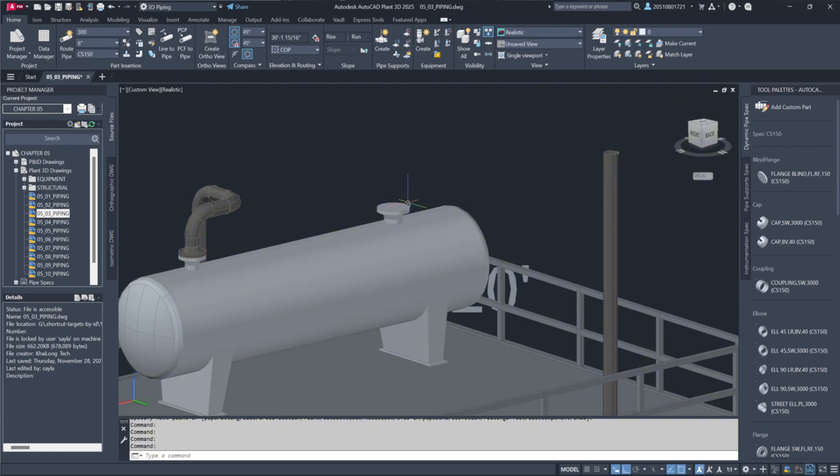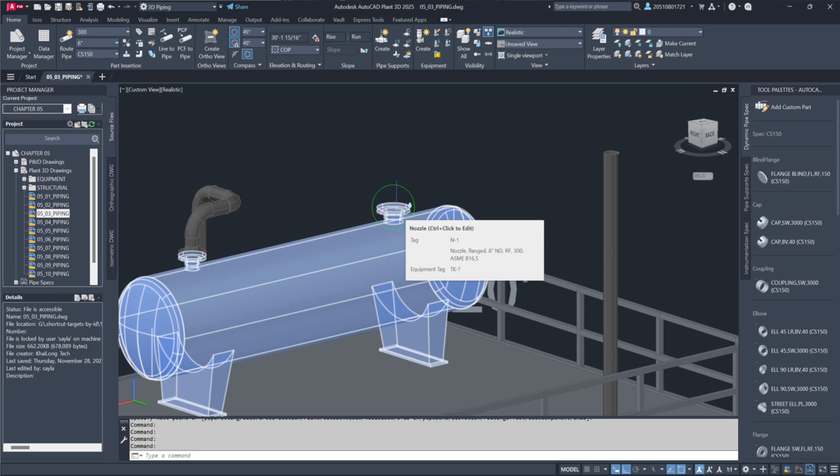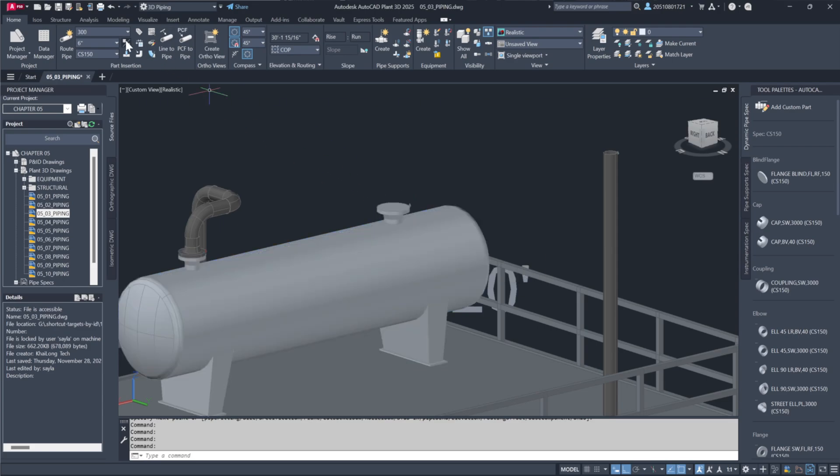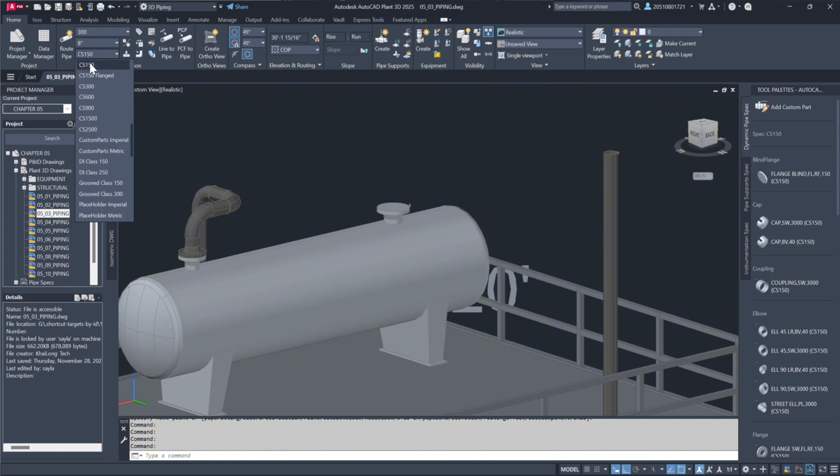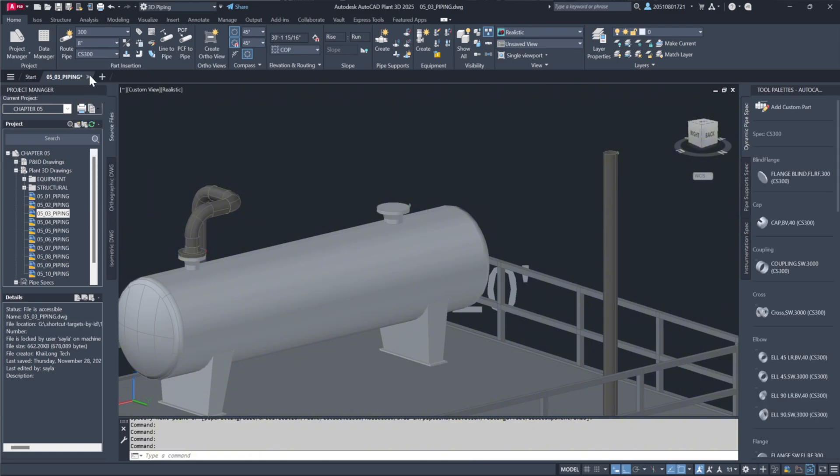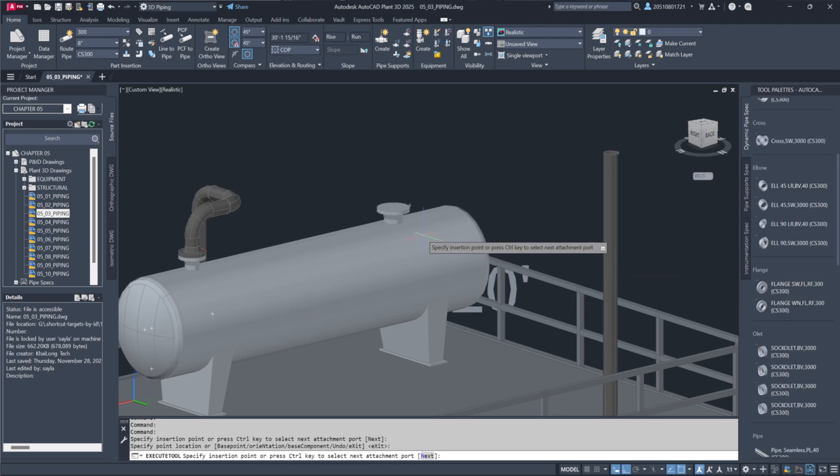I'll hover over this nozzle to examine the details. Here, we can see it's an 8-inch, 300-pound flange. I'll go ahead and change the setting to 300 for alignment. I'm going to select a weld neck flange from the tool palette, a 300-pound weld neck flange, and place it right here.